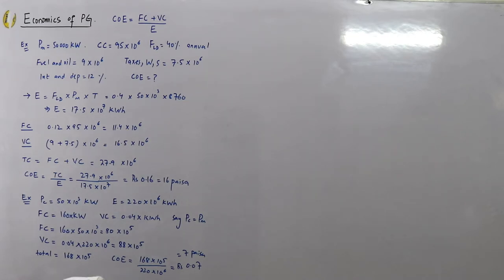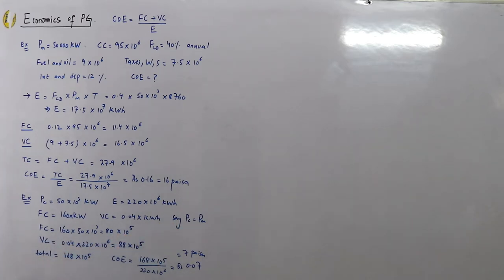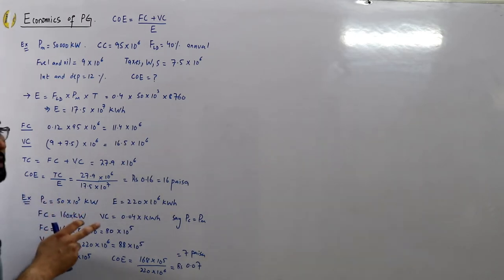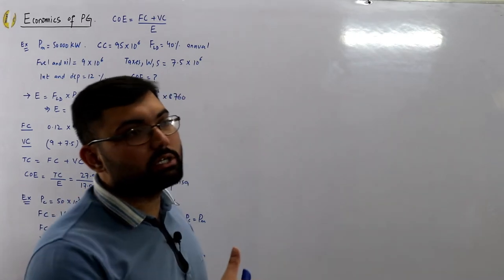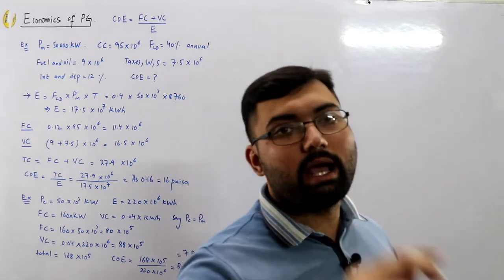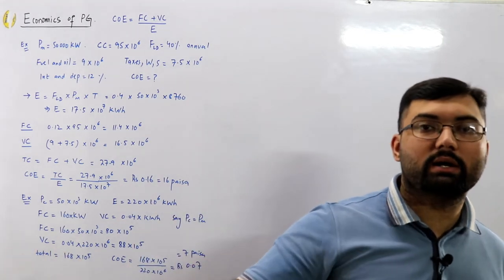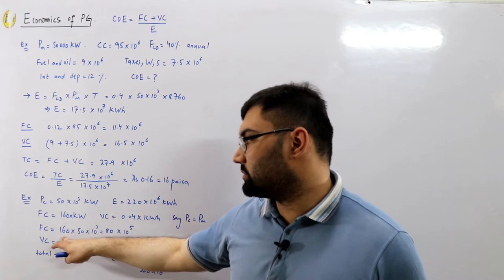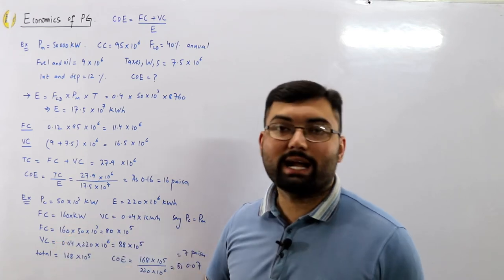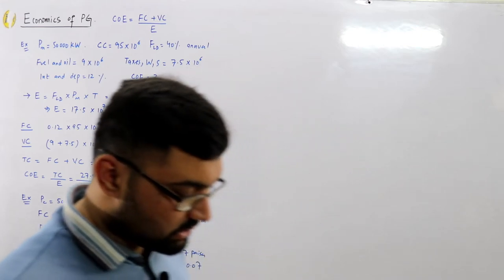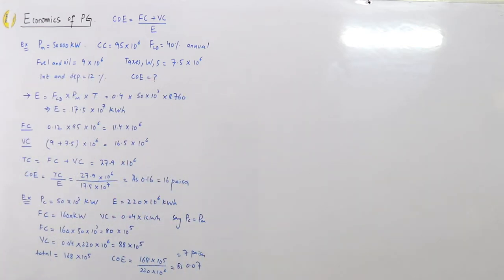Note: here I took installed capacity equal to maximum demand. If you want to include a reserve capacity as well, you must explicitly state that — for example, maximum demand is 40 megawatts and reserve capacity is 10 megawatts — then multiply 160 by 40 for the fixed cost calculation.